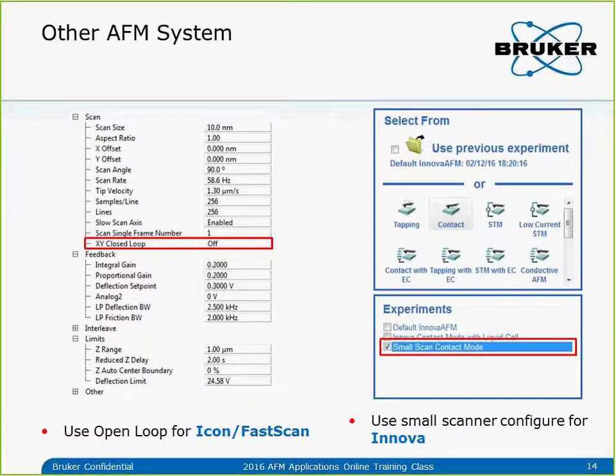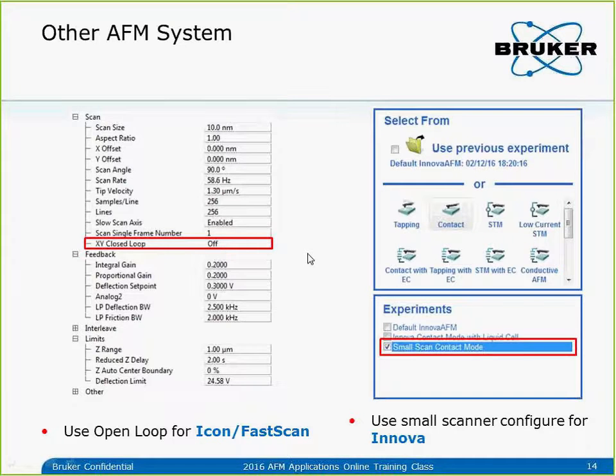The mica example I described used multimode with E-scanner, but you can do the same on FastScan or ICON with no problem, and also on Innova. For ICON and FastScan, they are typically set to XY closed loop on by default, which uses a closed loop sensor for linear movement. The closed loop sensor is pretty good on ICON and FastScan, but it's not really enough for atomic resolution imaging. So if you want to use ICON or FastScan for atomic resolution imaging, you definitely need to turn the closed loop off and use open loop. At small scan sizes like 10 to 15 nanometers, the piezo linearity in open loop is pretty good — you don't need to worry about linearity.